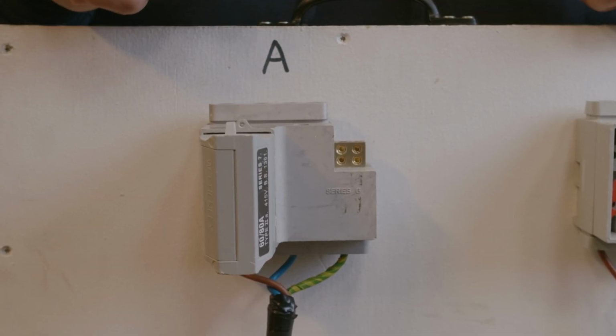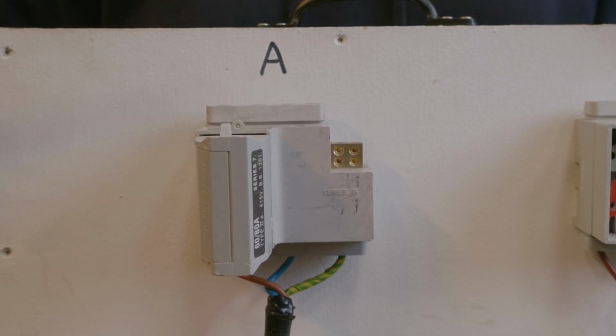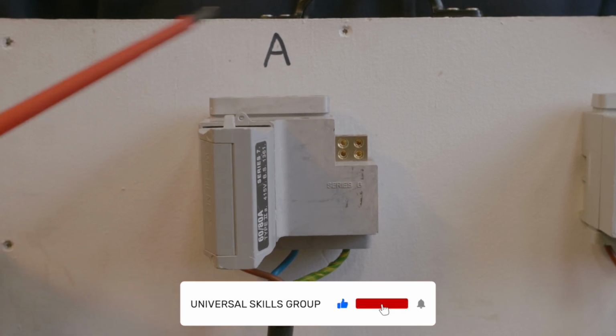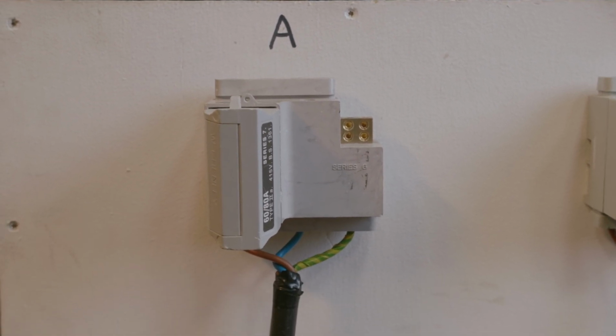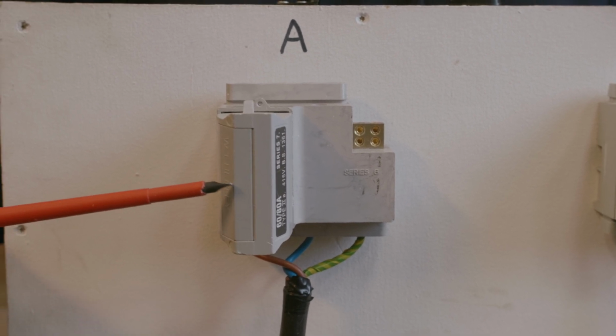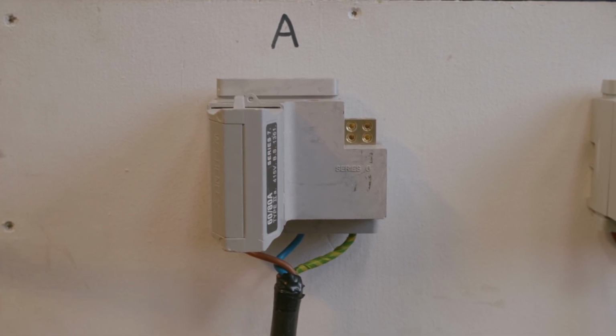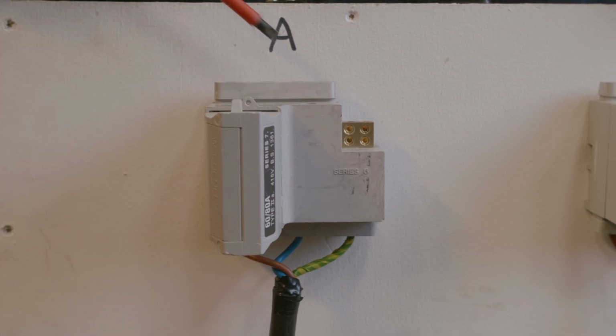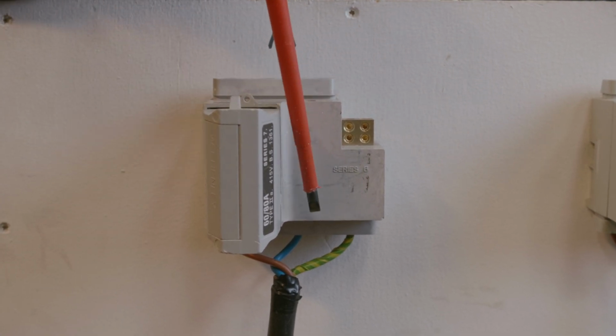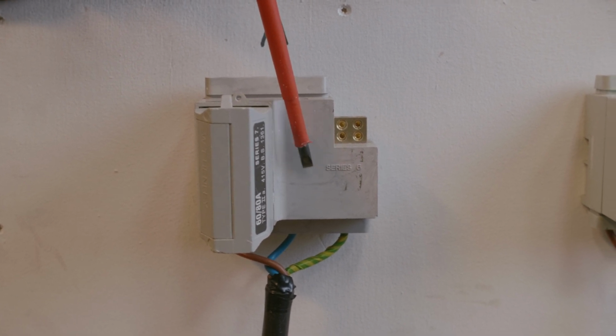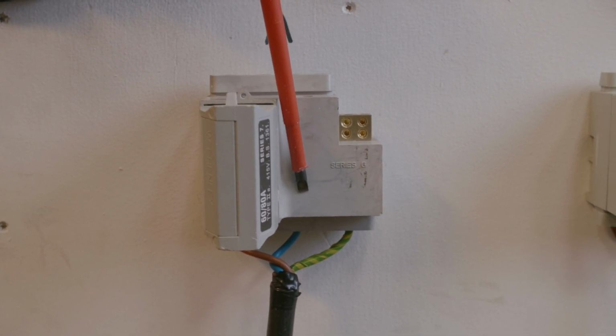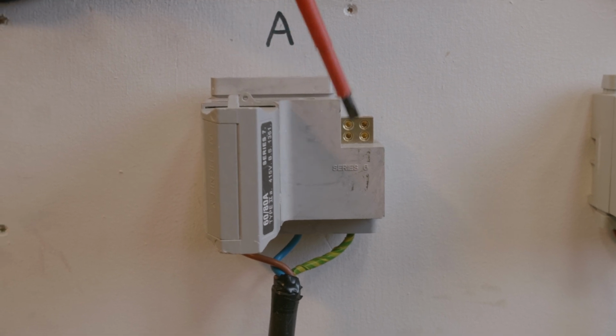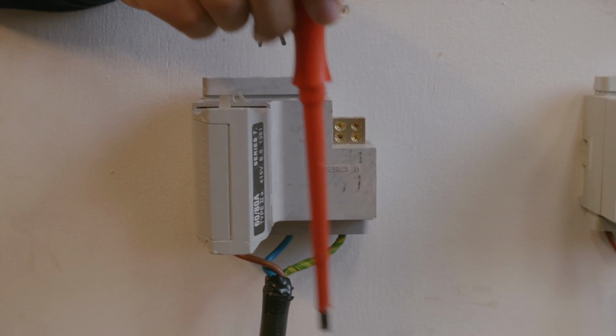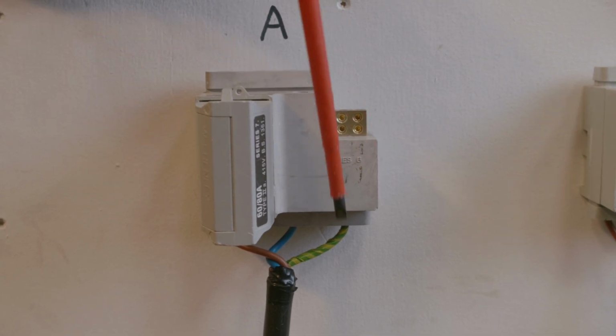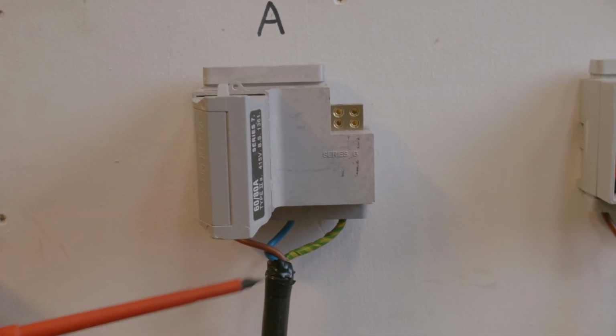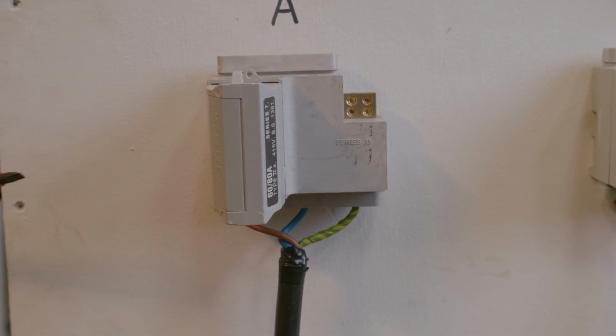Okay, so on this one here, to start with, we identify this point here as being the main supply, the main incomer to the property, and this is known as a cutout. The cutout comprises the main fuse and then the cutout point itself. We've got the cover there, which could be the combined neutral earth cover, or it could just be the cover for the separate neutral and earth. Also, because this is just a demonstration rig, we're not having a cover on the bottom, known as a crutch cover, so that's missing just for demonstration purposes.